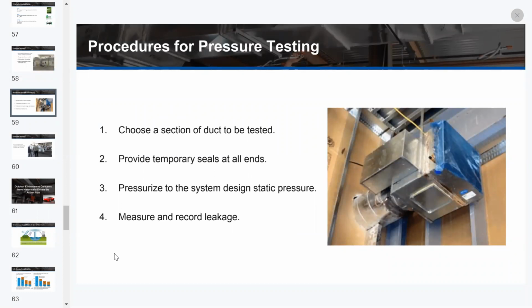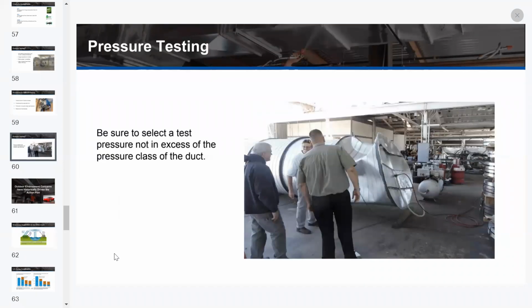So the proper procedure for this: choose that section of duct to be tested. That should be identified for you. Select a test pressure not in excess of the pressure class rating of the duct. Usually it's the actual operating pressure of that system. You're going to provide temporary seals at the ends of the ductwork because what you're testing is the duct system. Measure the pressure, and you're putting an amount of air into the duct system to get to a certain pressure. Let's say it's an inch of static, and you're measuring that through an orifice plate on a duct leakage tester. So the amount of airflow needed to keep that duct system at 1 inch of water gauge is what's leaking out. Pretty simple.